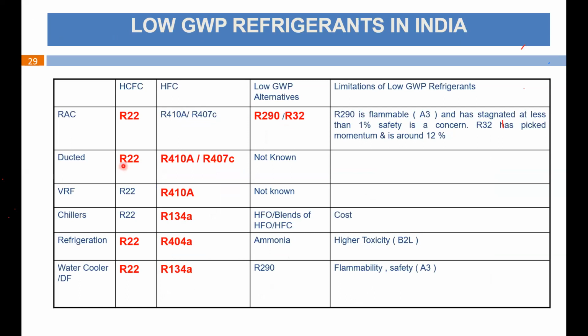For ducted kind of systems, R22 and R407C are used, but a low GWP option is not being used so far for ducted or package kind of systems. For VRF, R22 is not an option, so we are using R410A now. In chillers, R134A is being used, and the low GWP option is HFO or a blend of HFO and HFC, but the cost is a limitation. Cost is a worrying part for this.